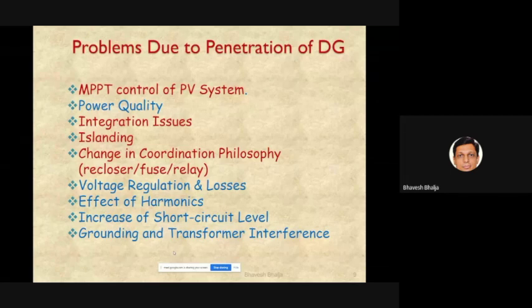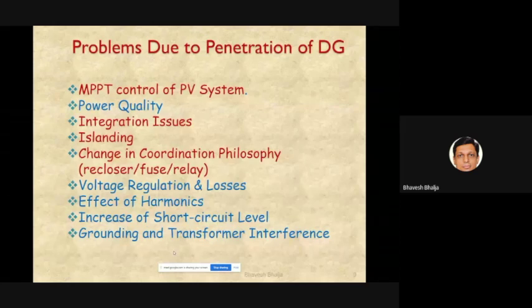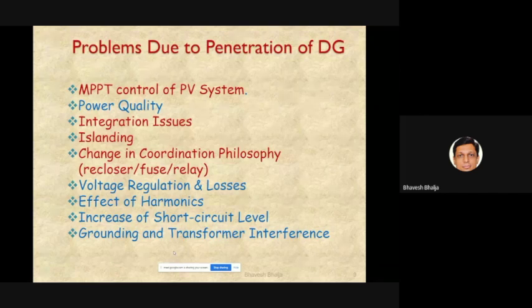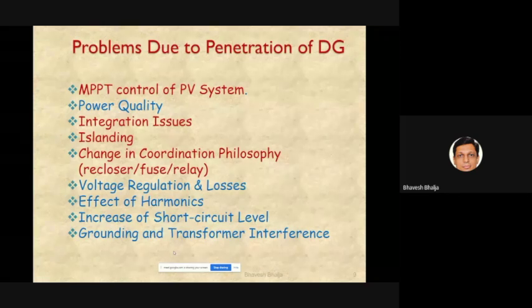When distributed generators (e.g., 10 DGs) are connected, they also inject current into the system. The utility power plus power from all 10 DGs are vectorially added, increasing the short-circuit level of the network. This means circuit breakers and isolators originally designed for the lower short-circuit level must be replaced, which involves significant cost.